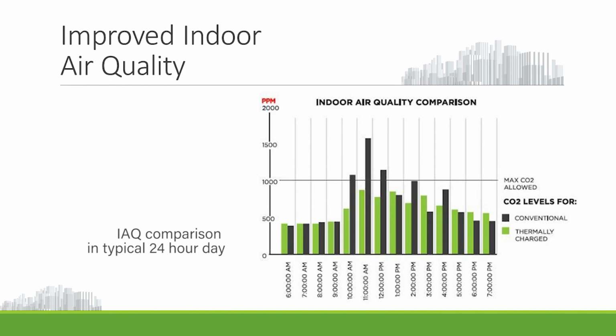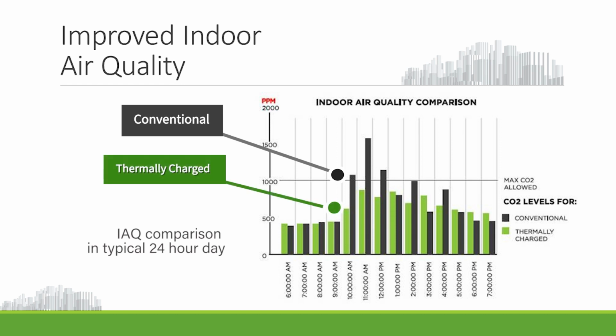We can see this in an actual setting. These two buildings in this graph are measuring the CO2 levels for a conventional building and an integrated ventilation design. The conventional building is the darker chart boxes. The integrated ventilation design is the lighter green elements. You can see that the building with integrated ventilation design never rose above the max CO2 allowed, while the other building did several times throughout the day, almost 4 times. These buildings can be used as a valid comparison because these two buildings actually sit next door to each other. One has integrated ventilation design, the other one doesn't.